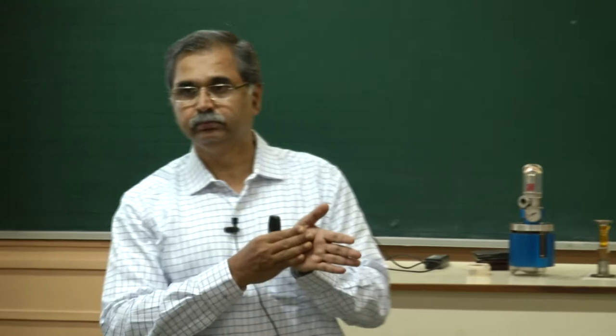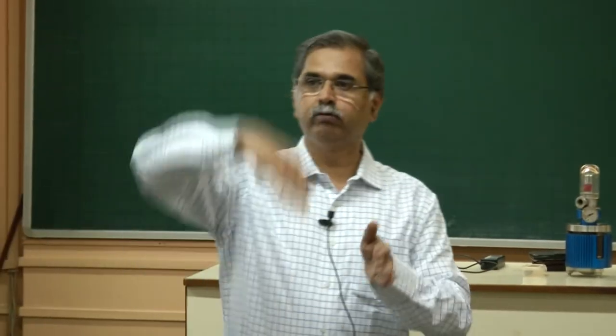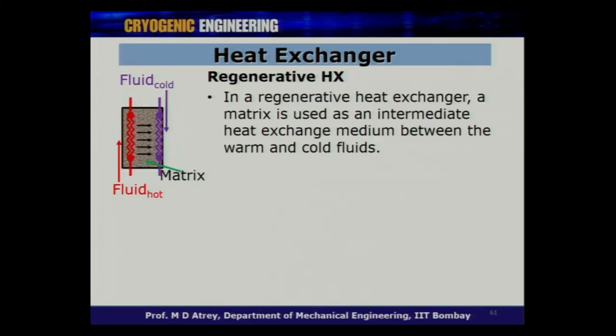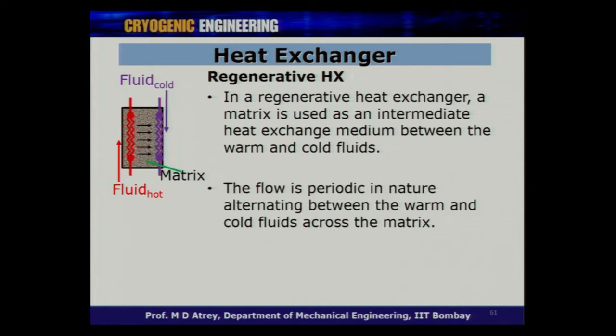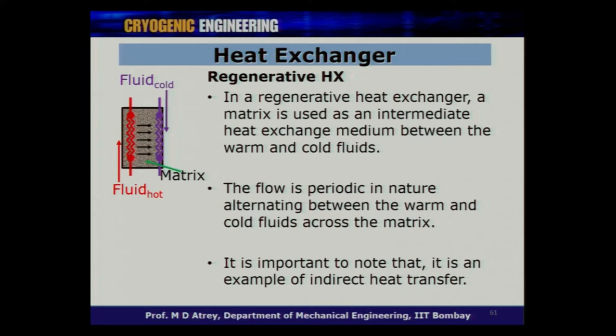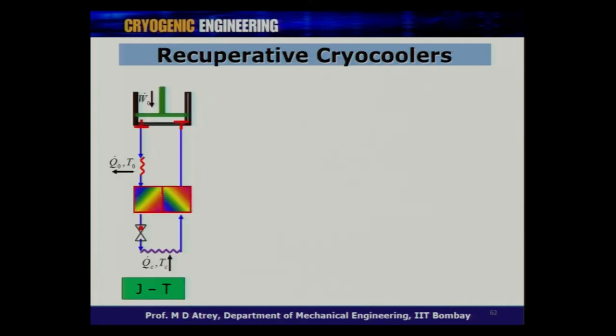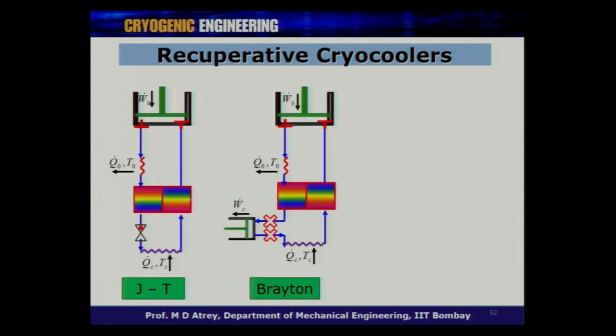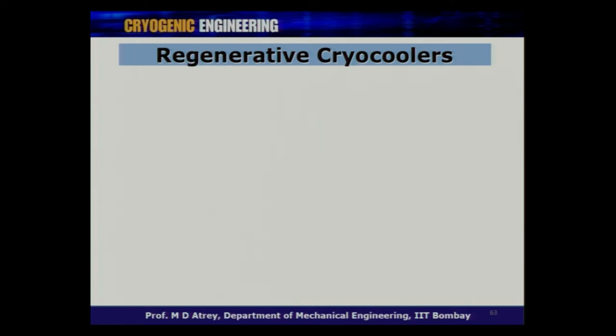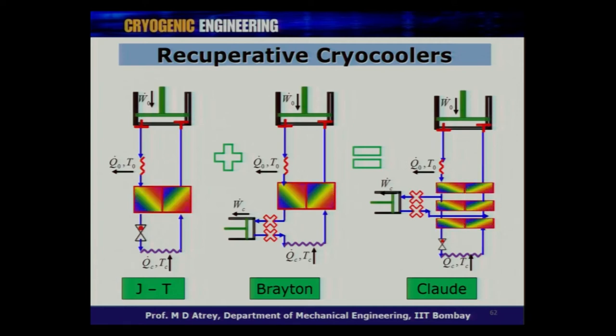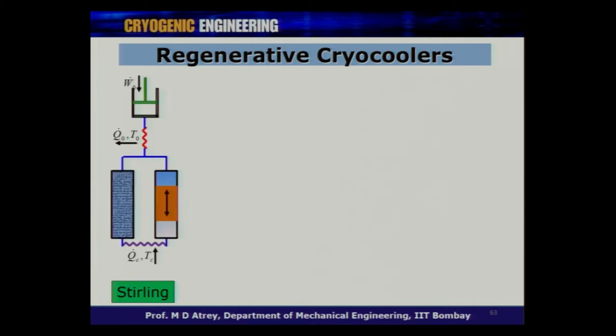In the regenerative heat exchanger, a matrix is used as an intermediate heat exchange medium between warm and cold fluids. The flow is periodic in nature, alternating between warm and cold fluids across the matrix. This is indirect heat transfer — no direct exchange between fluid A and fluid B, and they are not moving simultaneously. The refrigerators at home (Linde-Hampson, Brayton, Claude cycles) are all recuperative. Regenerative heat exchangers are used in Stirling coolers, Gifford-McMahon coolers, and pulse tube coolers.